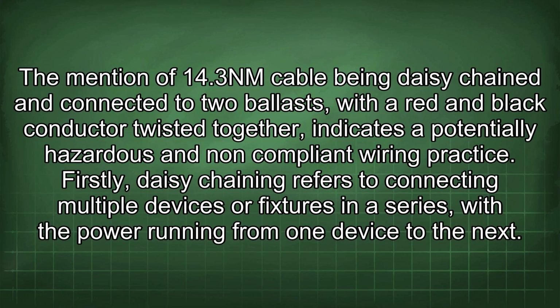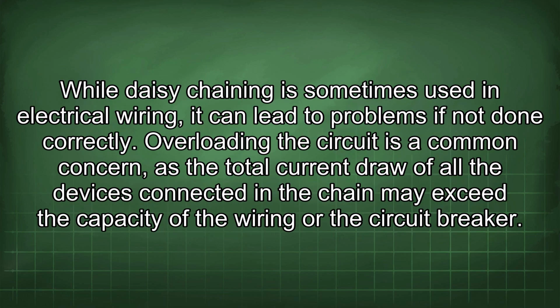The mention of 14/3 NM cable being daisy-chained and connected to two ballasts, with a red and black conductor twisted together, indicates a potentially hazardous and non-compliant wiring practice. Firstly, daisy chaining refers to connecting multiple devices or fixtures in a series, with the power running from one device to the next. While daisy chaining is sometimes used in electrical wiring, it can lead to problems if not done correctly. Overloading the circuit is a common concern, as the total current draw of all the devices connected in the chain may exceed the capacity of the wiring or the circuit breaker.